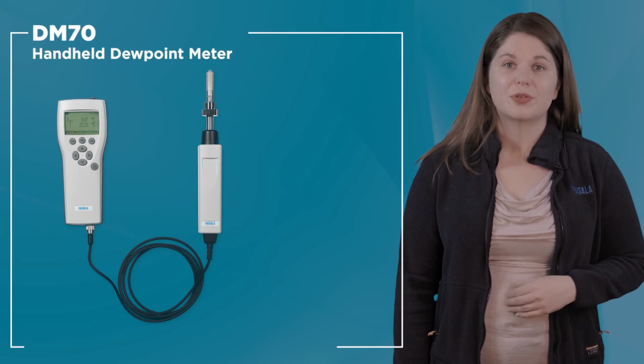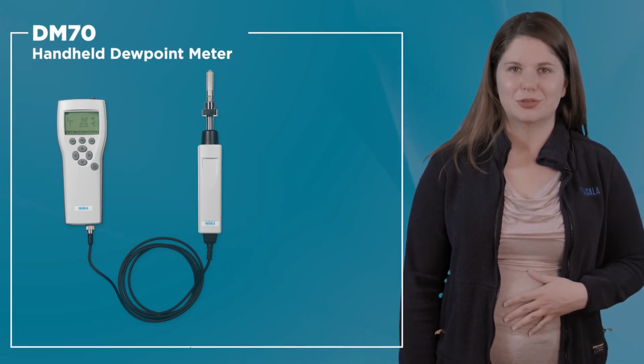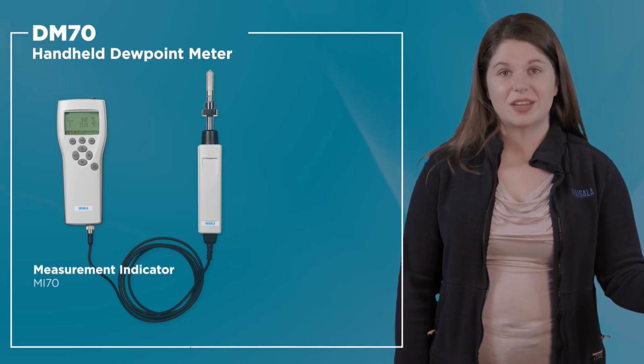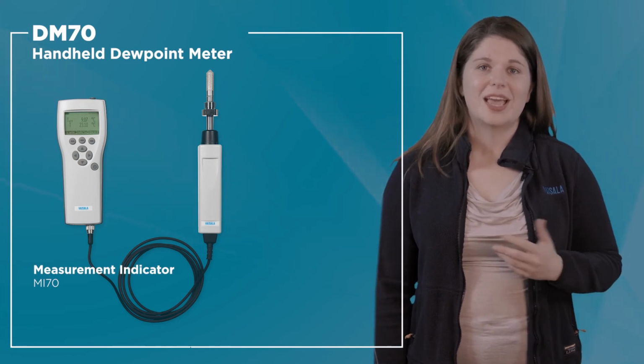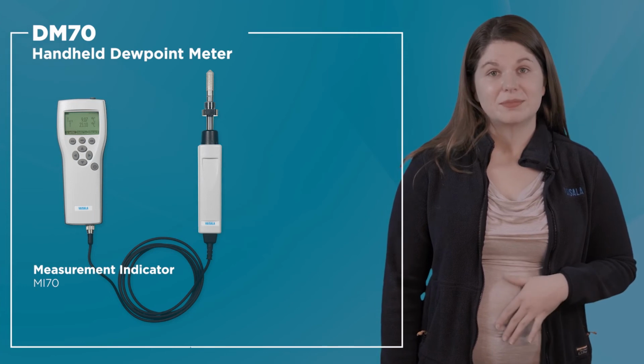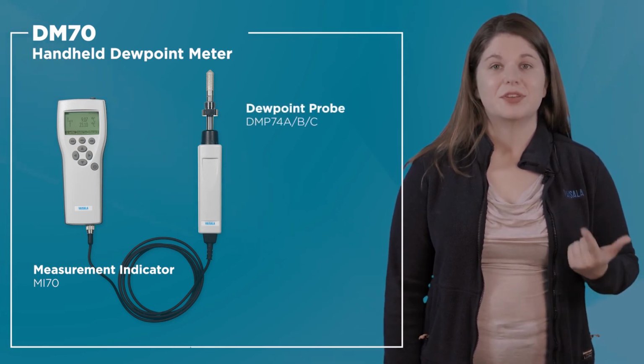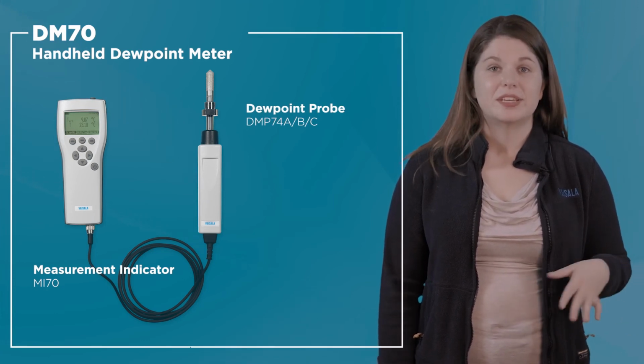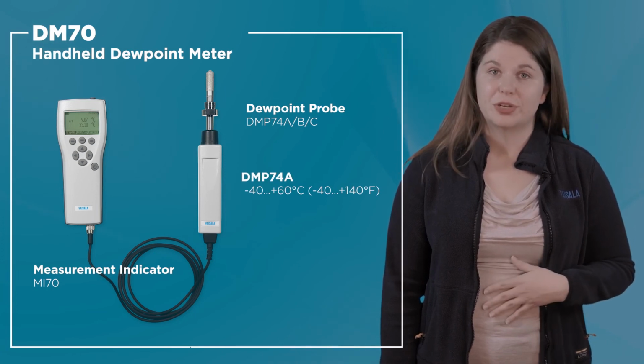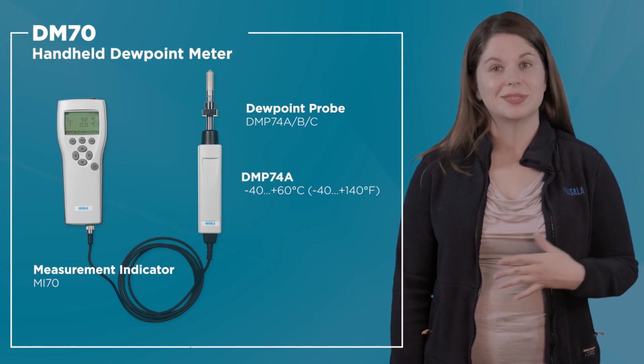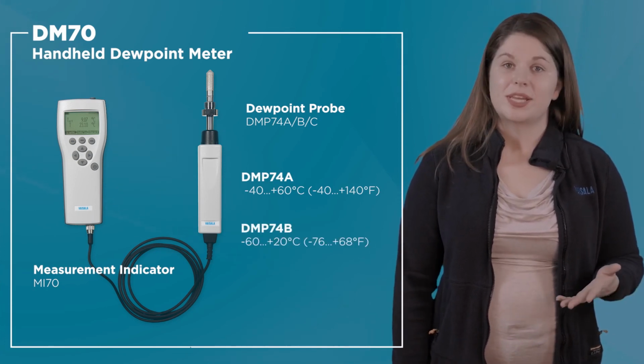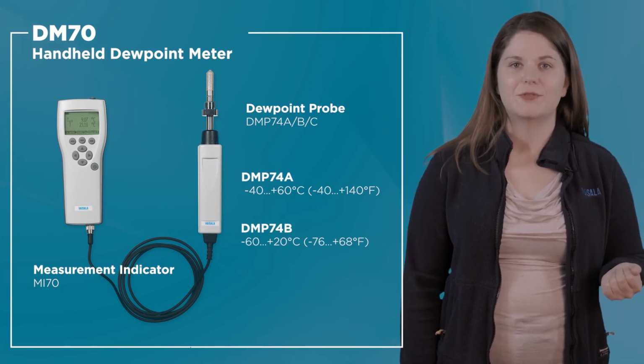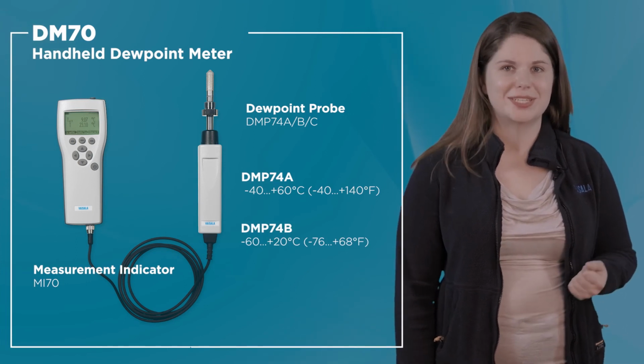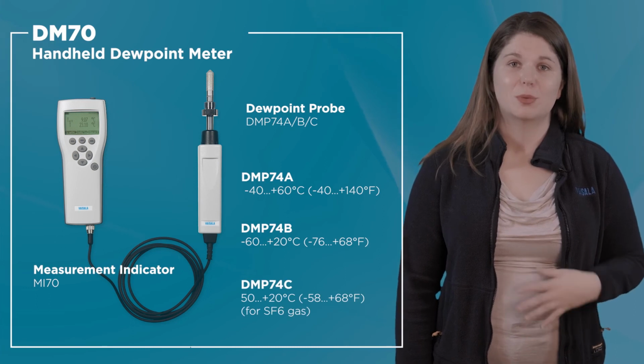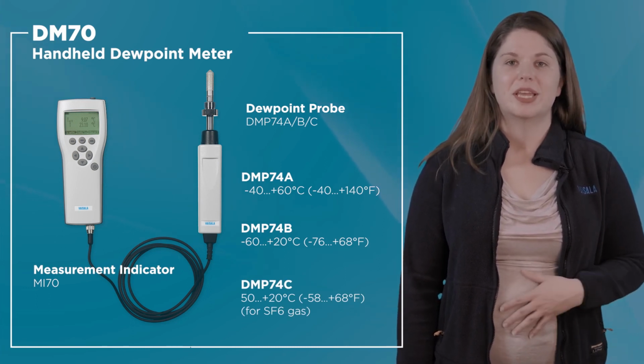While all the products I've discussed so far can be used for permanent installation, we do also offer the DM70 handheld dew point meter as our portable solution. The DM70 includes an MI70 indicator, which provides a display, user interface, and powers the probe. Standard probes offered with the DM70 are the DMP74A, DMP74B, and DMP74C. The DMP74A is appropriate for spot checks on refrigerant dryer systems and measurements in the -40 to +60 dew point range. The DMP74B is the go-to for spot checks on desiccant dryer systems and for measurements from -60 to +20 degrees C dew point. And the DMP74C probe, which is a specialized probe designed for moisture measurements in SF6 insulating gas.